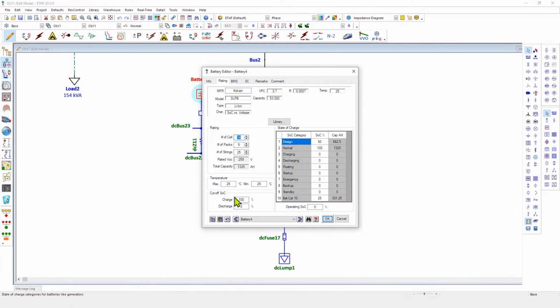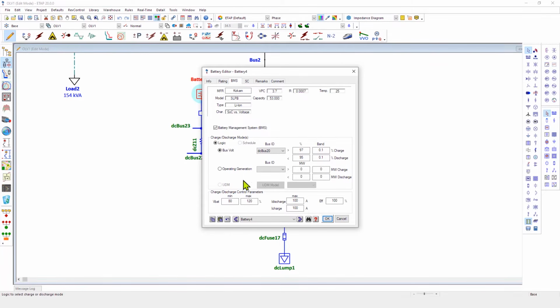We have also added in additional options such as the cutoff of the state of charge. This means that the battery stops charging when it reaches 100% state of charge, and it stops discharging when it reaches 0% state of charge. And of course, these values are customizable. We will also utilize a battery management system that allows the user to define the control bus voltage as well as the characteristics of the BMS, such as the ability to charge the battery above a certain voltage range or discharge the battery when below a certain voltage range.